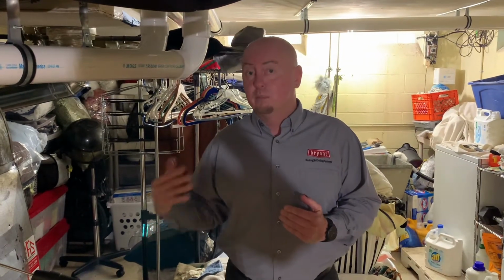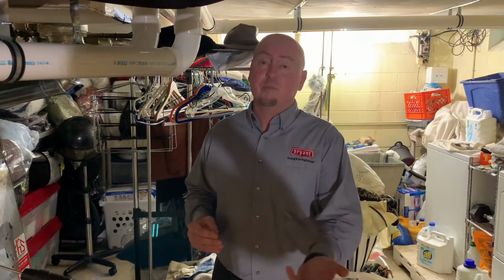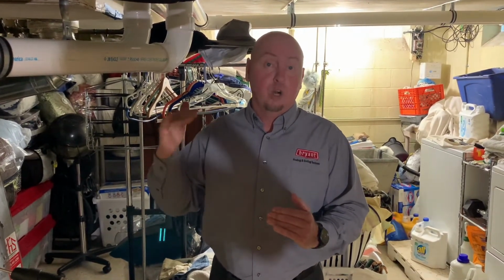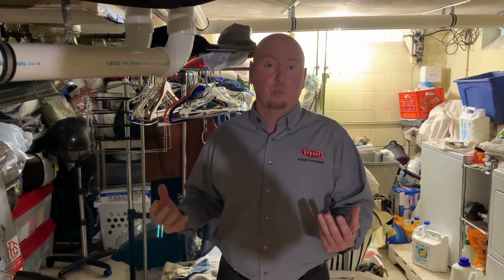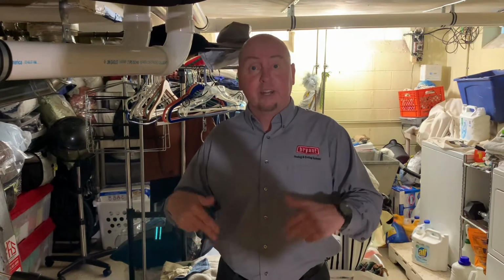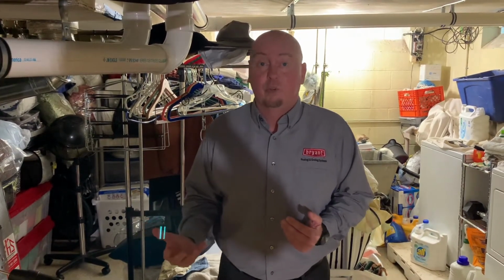Let's say it's 7% O2. But when the blower comes on the furnace, what you're looking for is a change in oxygen. If I'm running at 7%, the blower comes on, and all of a sudden it goes up to 10, 11, 12%, that could very well indicate that there's something wrong with the heat exchanger when the blower comes on, that you're putting air into the heat exchanger. That's where you're picking up the additional oxygen.